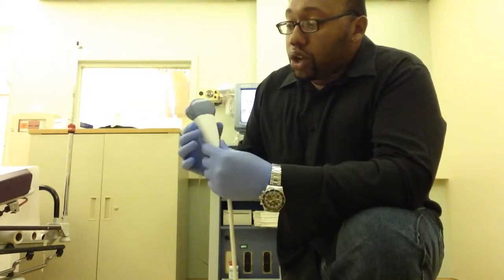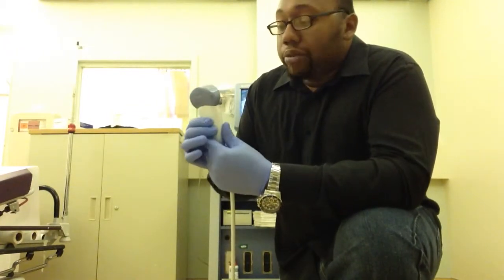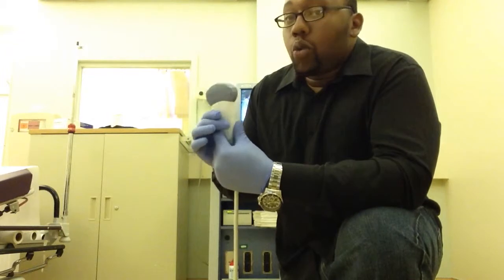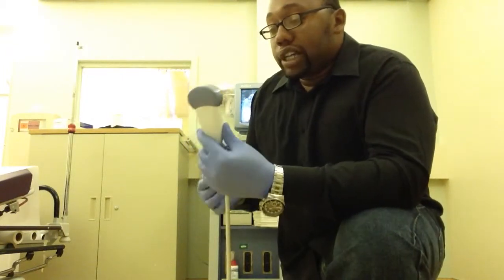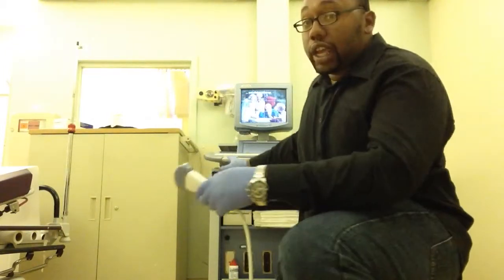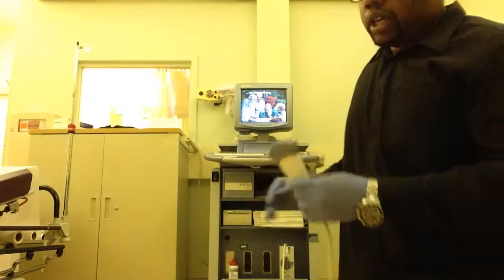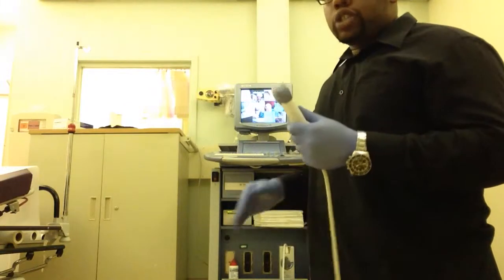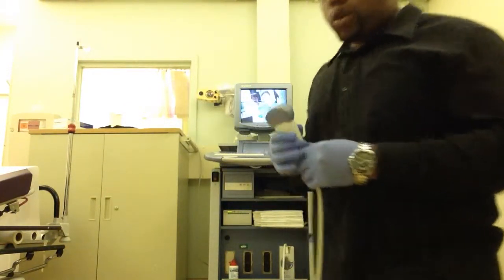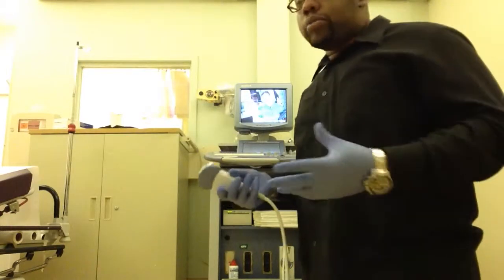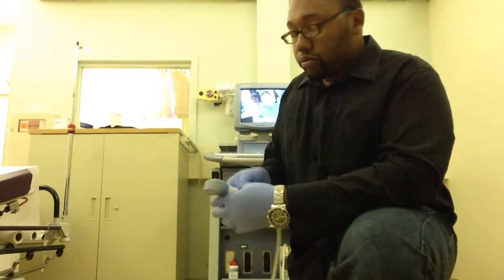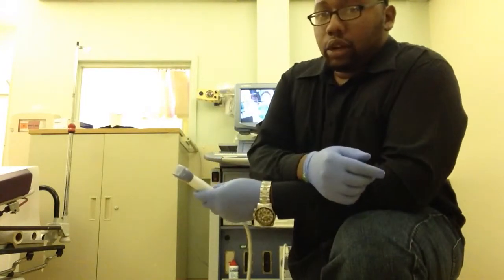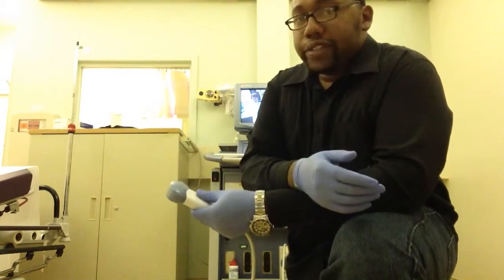Okay? So in terms of calibrating these transducers, what we use is a water bath. At the time we're calibrating these transducers, they're not even hooked up to the ultrasound unit right here. We disconnect the probe and connect it to a synthesizer and an amplifier, because we're going to produce our own voltage across the transducer to create an ultrasonic wave of sound.